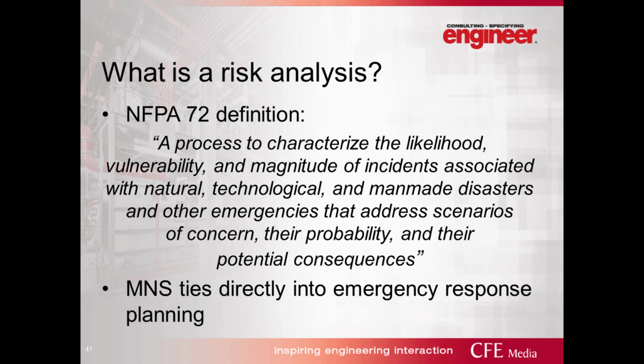So what is a risk analysis intended to do? It's a process that is thought through to characterize the likelihood, vulnerability, and magnitude of incidents associated with natural, technological, and man-made disasters and other emergencies that address scenarios of concern. The one thing that NFPA 72 does not intend is that the committee does not intend a thesis be developed to design a mass notification system. Language was added in the last cycle of 72 that recognizes that there might be an emergency response plan in place that addresses the hazards. So some level of risk analysis has been performed. The mass notification system can then be designed to address the communication needs of that emergency response plan.